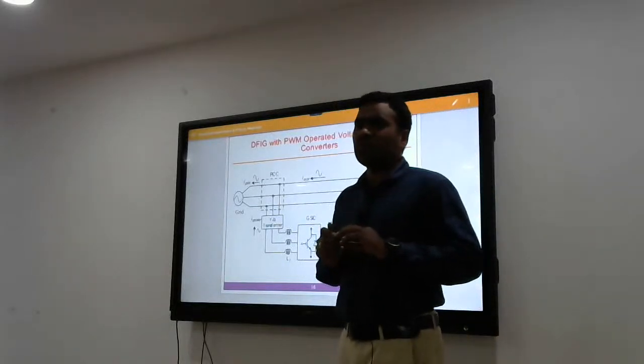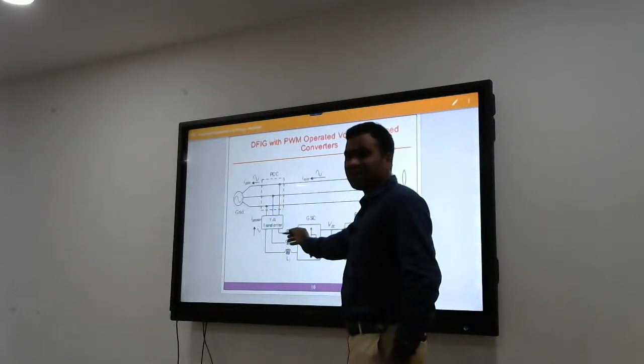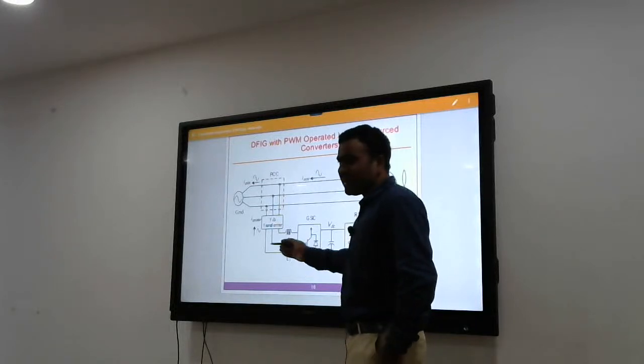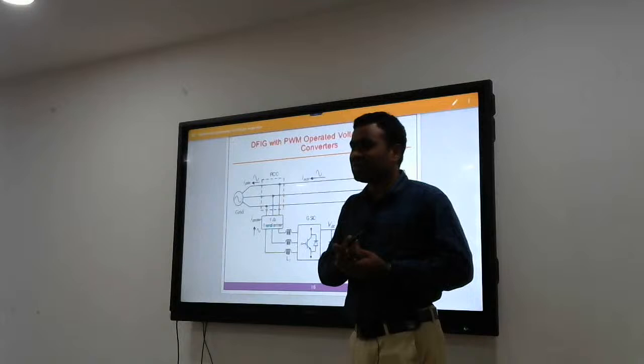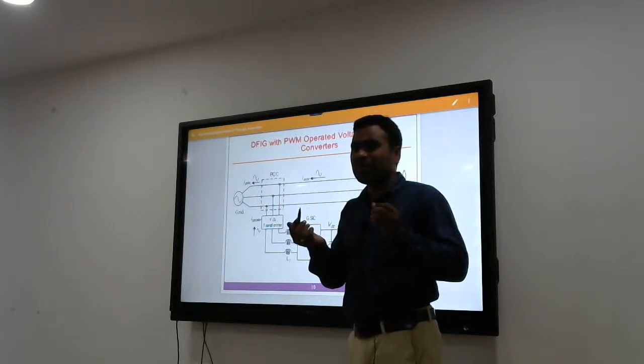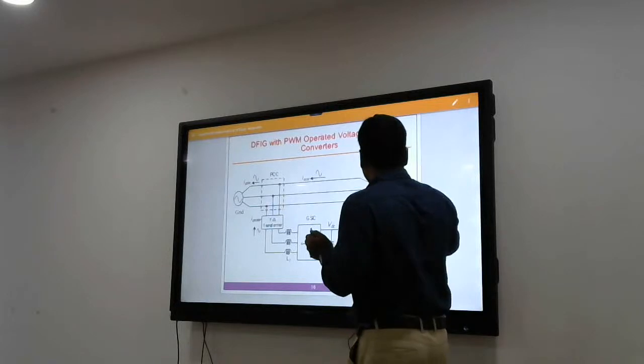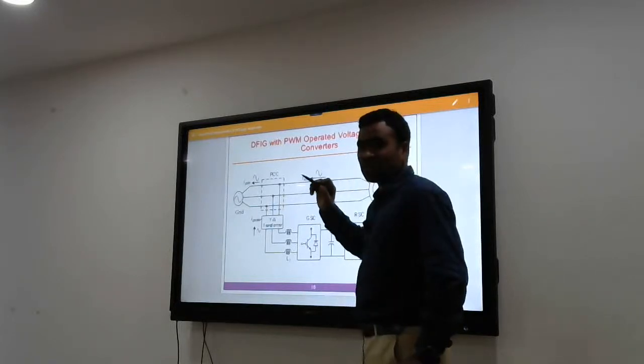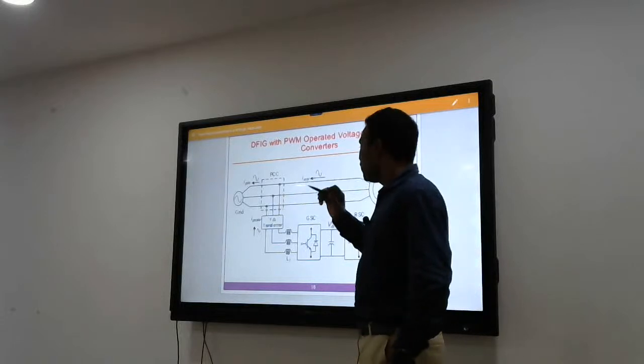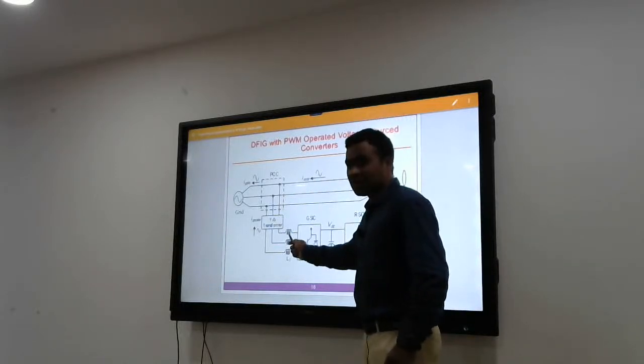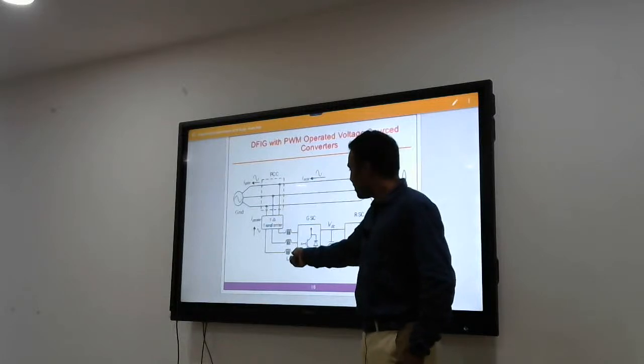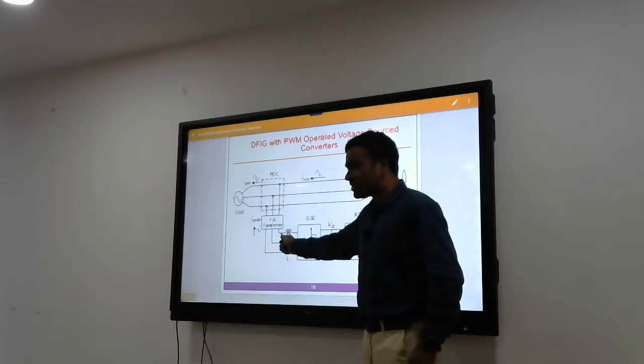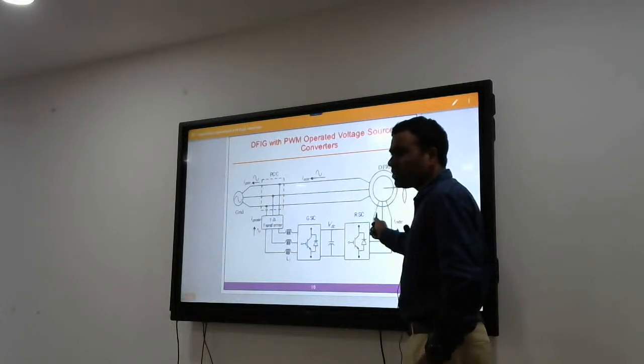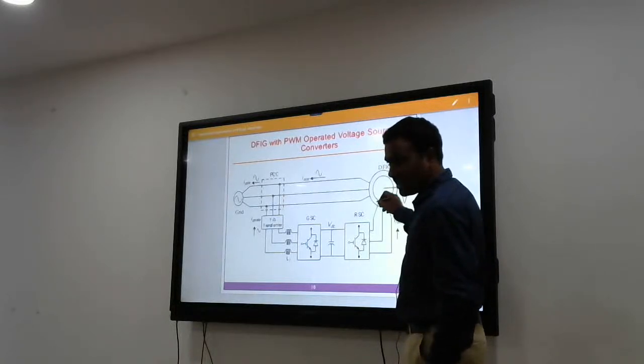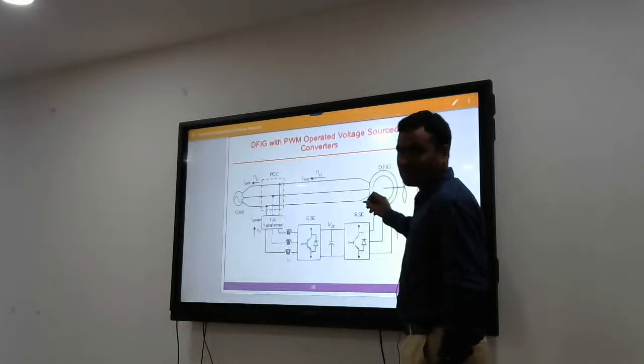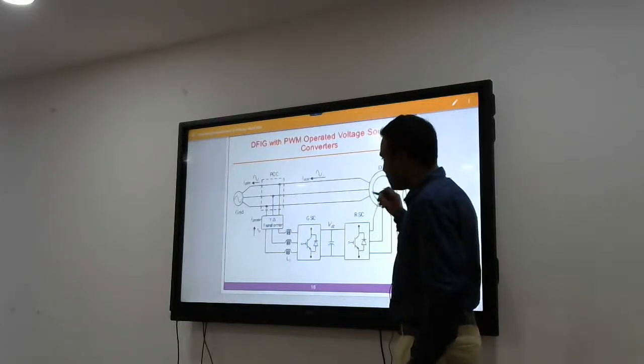Theoretically, you may say you get voltage from DC to AC, but you may have studied PWM, pulse width modulation. If you know PWM, then the generated voltage will be in pulses, but it's not pure sinusoidal. To get it into a sinusoidal, you need some filters, and these are the filters to convert these pulse width voltages into sinusoidal voltage. So this is a filter here. Then you can ask why there is no filter here. Here you have the rotor winding inside, and the rotor winding has some inductance, so you don't require any filter here.